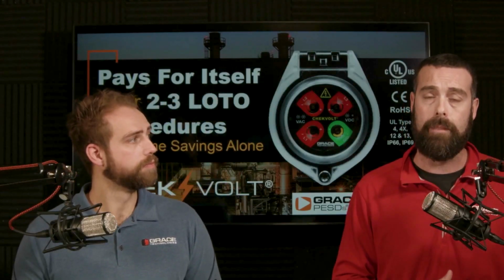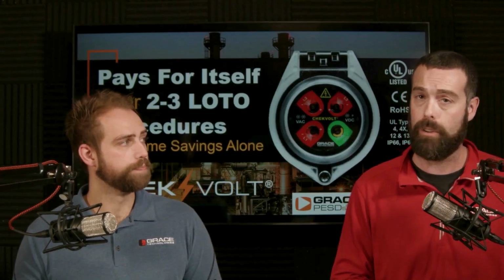And what I'm about to say will also tie into a question here. It says, apart from its listing, how does this meet the requirements of NFPA 70E? So Ben, you kind of alluded to that. Again, our permanent electrical safety device is line voltage powered, so there are no batteries associated with this device. As I mentioned before, it is built with a potted construction and current limiting resistors. And if you opt for the lower voltage device, it will have that 10-to-1 voltage divider.